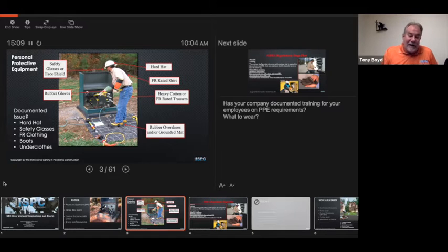Basically that is because when you're handling a hot stick, you need to be in positive control of the energized conductor, whether it's an elbow or overhead jumper or whatever. You have to be in positive control, and sometimes wearing rubber gloves does not allow that. I was a little bit thin back in my line worker days. So when it came to some of those big elbows, I actually had to take the stick and put it up under my arm to pull it. So what are rubber gloves doing? I'm not going to get into the electrical properties, but that's some of the things that we cover when we're on site.